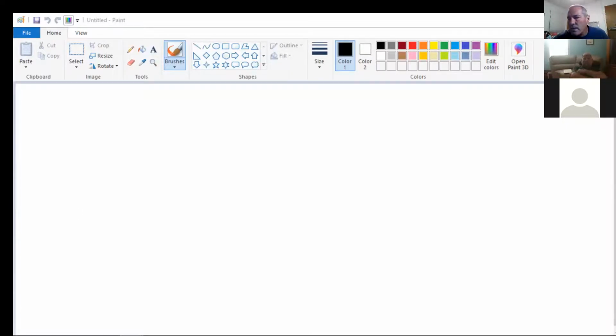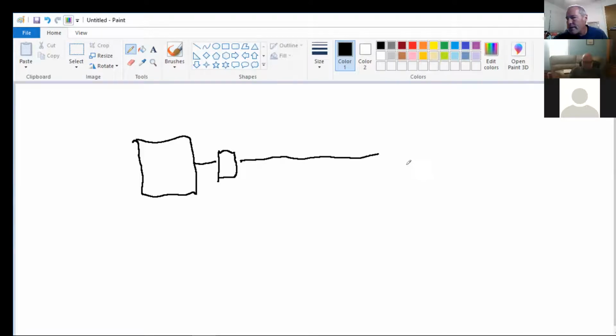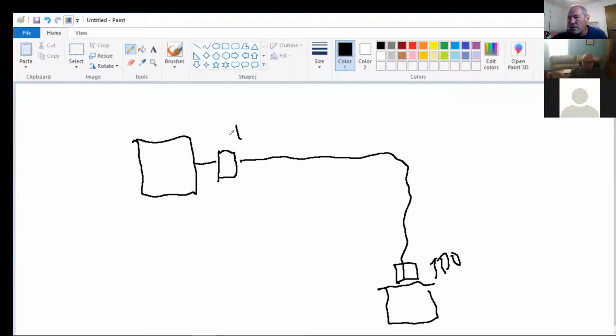Remember, in transmission, use this when you have the capability. We started enjoying it very much. If I've got a transmission substation—I'm just going to draw a breaker on one side, and the breaker's on this side, and I've got a ton of line that comes down here. I'm drawing from a distance, sorry for the squiggly stuff. And I've got another substation down here, with another breaker on this side. So I've got full line protection, the TPU on both sides, and this is mostly for transmission lines, which, unlike distribution, don't tap a lot.